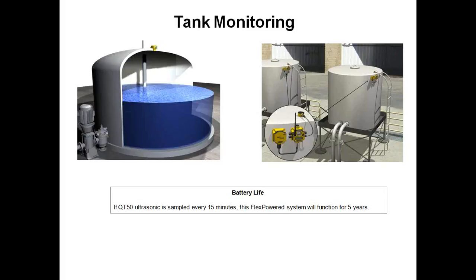Tank monitoring is another good one. This is one we're showing with an ultrasonic sensor up at the top of the tank, basically looking down, reporting back level on an analog signal. And then out on the tank, you would have a node with a battery module, and again, an ultrasonic sensor here. To give you an idea about that battery life, the QT50 is a larger ultrasonic sensor that will do about a 28-foot range. And if we put this out on the tank, sample that analog value every 15 minutes, we'll get about 5 years out of the battery, basically driving this whole setup here.